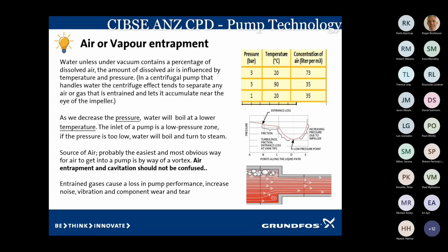Because what you're doing is, you remember going back to that pump curve when you saw that NPSH requirement curve. When you grab that valve and you actually shut it off, you reduce the flow, you're dropping the NPSH requirement, and you're getting back to a balance where the atmospheric pressure is greater than the net positive suction required, so the cavitation goes away. If the noise doesn't go away, it can be air entrapment, because they sound very similar, but the air entrapment won't do as much damage as the cavitation will. That's for sure.